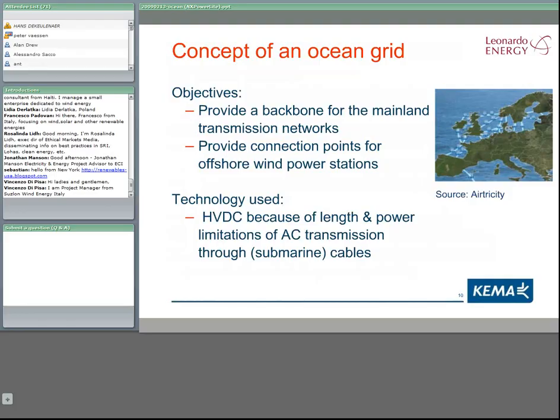As said earlier, the technology which has to be used will be HVDC because of the length and power involved. It's physically very difficult, I must admit not impossible, but very difficult to transmit AC power through cables longer than, say, 30 or 50 kilometers. So when you talk about submarine cables, you will soon end up with HVDC cables.